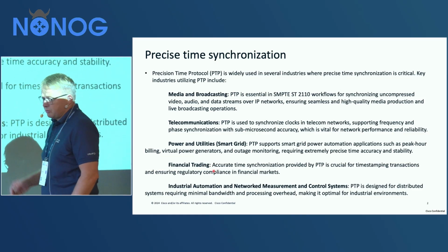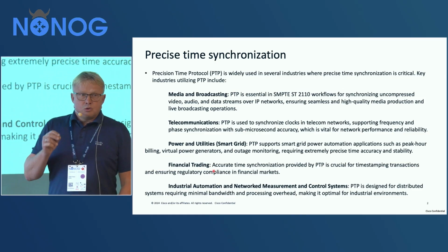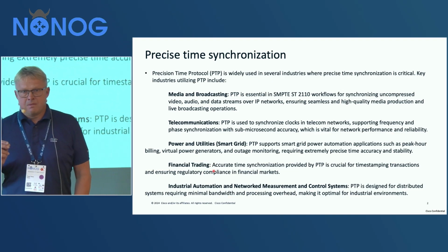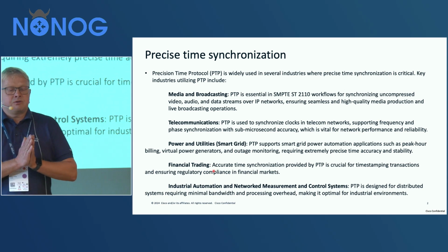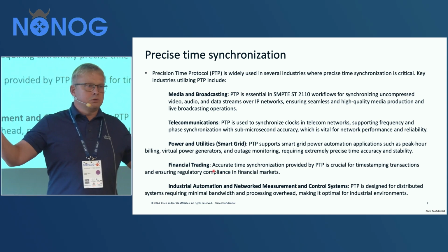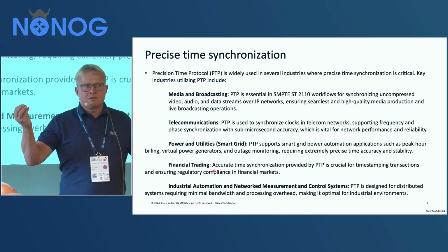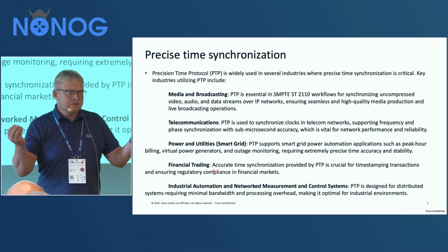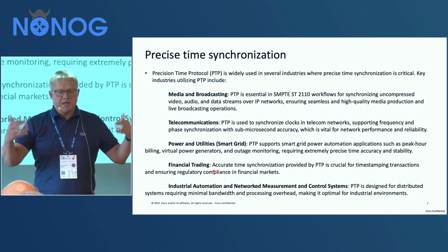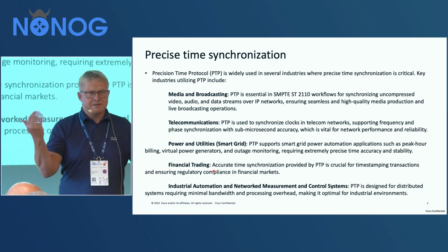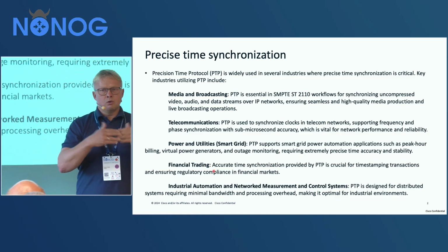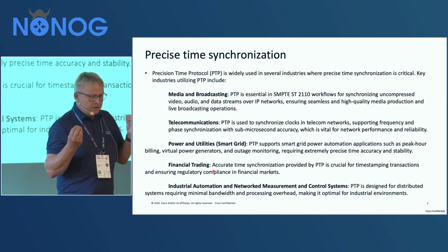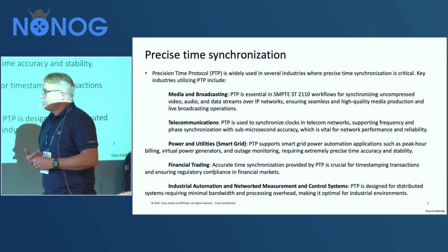My favorite customer group these days is the power utilities. All substations within the Kingdom of Norway need accurate time. Think of a transmission line, 400 kilovolt. There are protection units in both ends of these power lines. Those units need synchronous time to be able to trip, as we say, switching off the fuse at the same time. If they don't, the whole thing can catch fire. So within those kinds of industries, accurate time and frequency is super important.